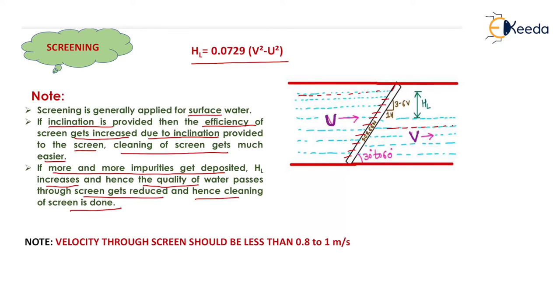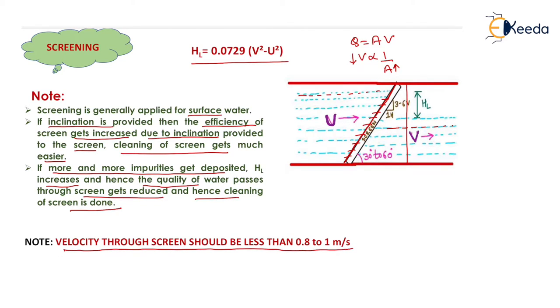Using the continuity equation, Q = Av. If discharge is constant, velocity is inversely proportional to area. Due to the inclination, surface area increases, so velocity decreases before the screen. After screening, the surface area decreases again, so velocity increases. We want a smaller velocity before the screen so that all the impurities will be removed from the water. The velocity through the screen should be less than 0.8 to 1 meter per second.